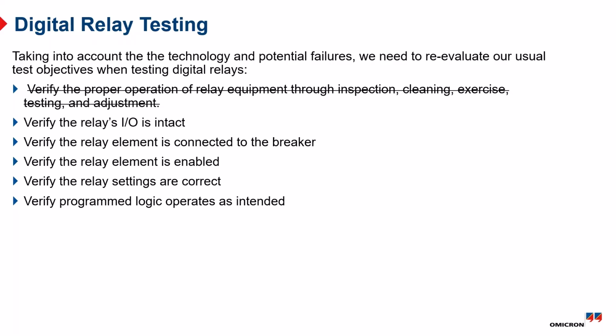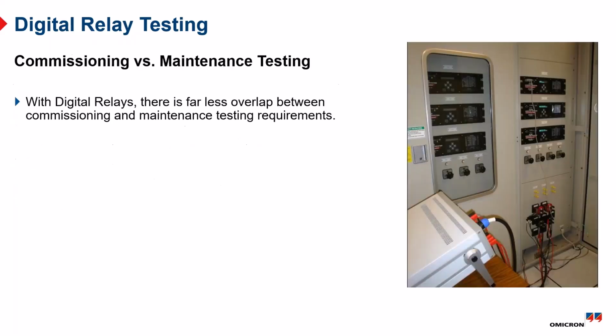Also, verify the program logic operates as intended. A lot of those things we saw earlier in the SV there, where I have an under voltage element that's supervised by breaker position and loss potential blocking logic. Any asterisk instead of a plus or whatever in that logic equation can cause a relay to either operate when it's not supposed to, or not operate when it is supposed to.